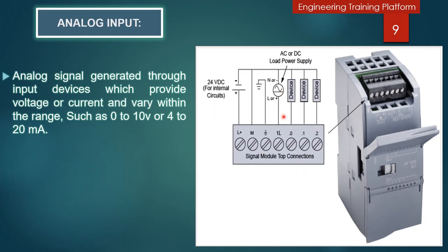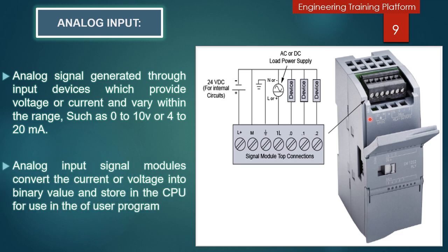The analog input signal module can be operated on a DC or AC power source. For the DC power source, the negative supply is connected to the device. If you select the AC source, on the negative side you connect the neutral, and on the positive side you connect the line. An analog input signal is generated by a sensor that provides voltage or current that can vary within a range, such as 0 to 10 volts or 4 to 20 milliamps. The analog input signal module converts the current or voltage to a binary value that the CPU stores for use in the user program. The number of bits in the binary value is referred to as the channel resolution.